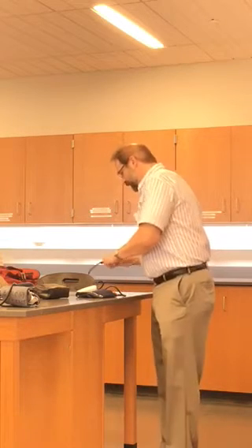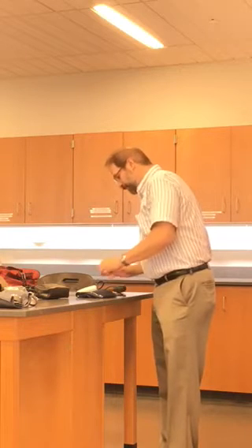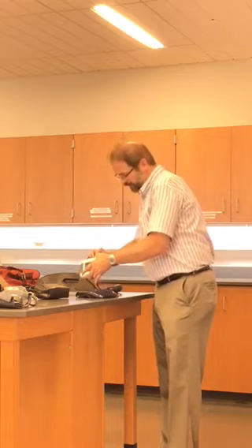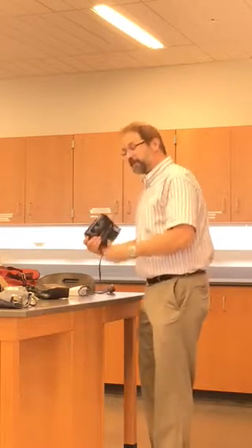So there are a couple of things you have to make sure of. You have to make sure that the valve is closed. Sometimes it sticks, so work it a couple of times to make sure it's closed. And then where this goes into the machine, sometimes that comes loose, so make sure that's fully seated in there. If it leaks, it won't register. And then it's time to put the blood pressure cuff on.